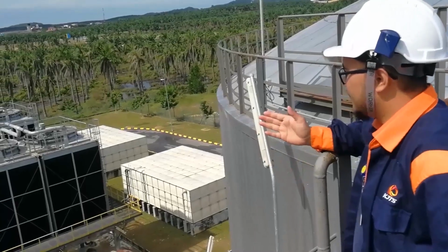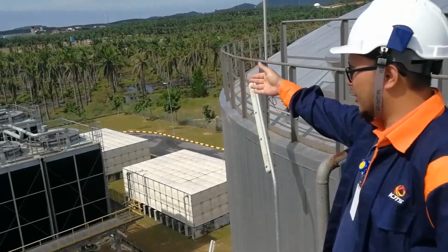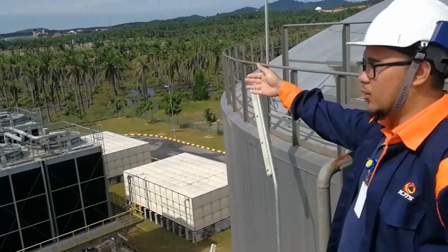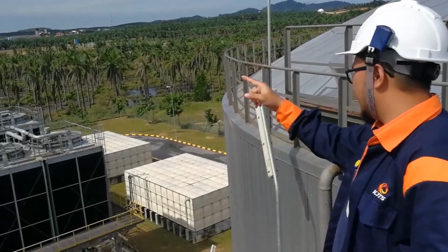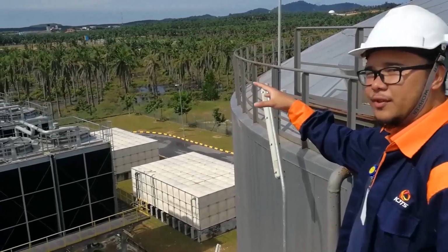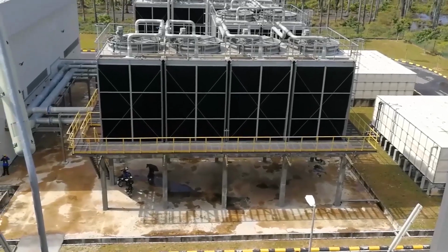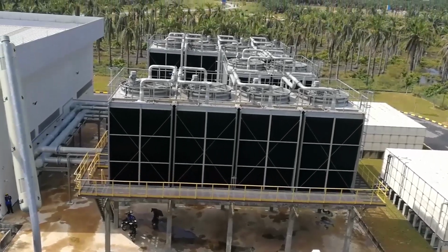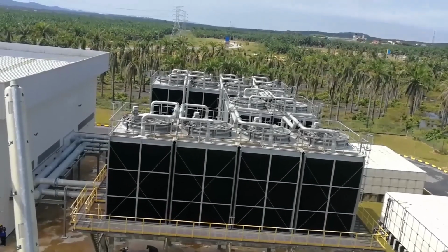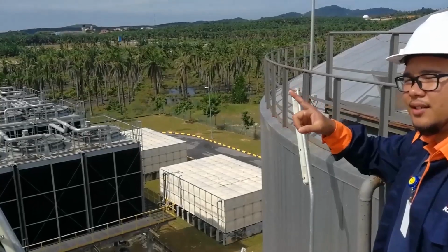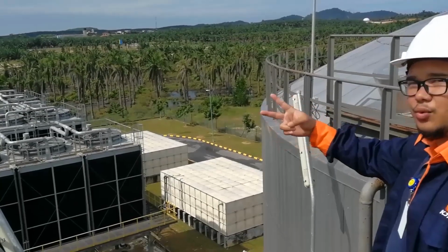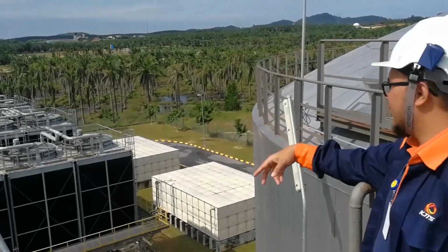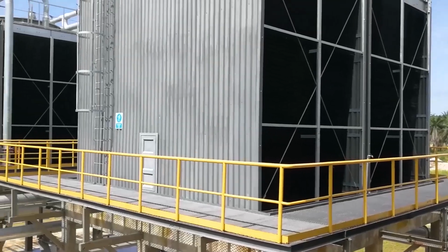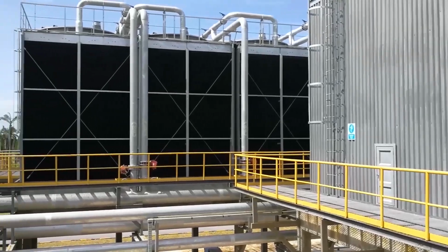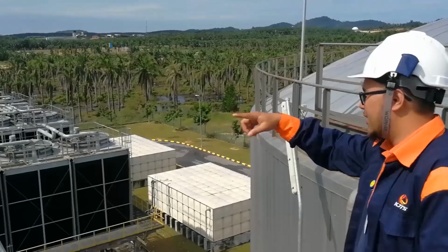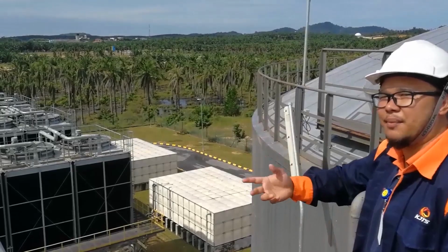Here you can see our district cooling plant's cooling towers. We have 10 units of cooling tower, and 2 units are for standby. We have 5 chillers, and each chiller must have two cooling towers, two units of cooling tower. Two units in the middle are for standby for chiller 3, the standby chiller.